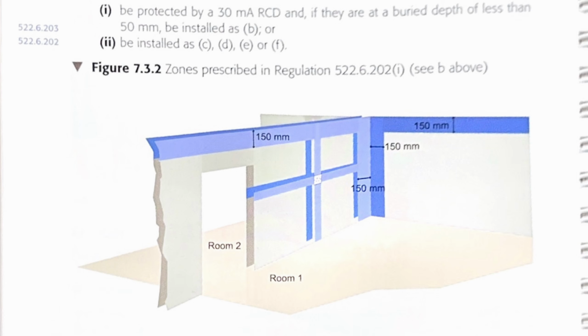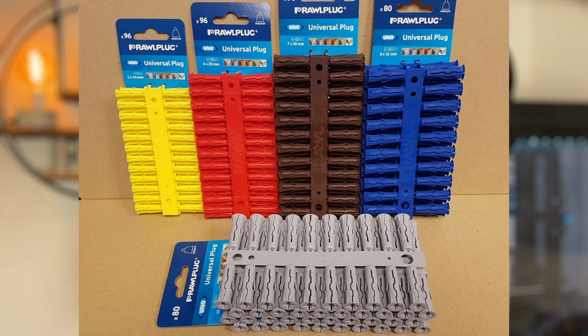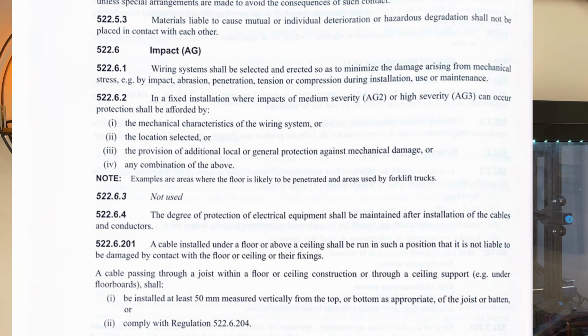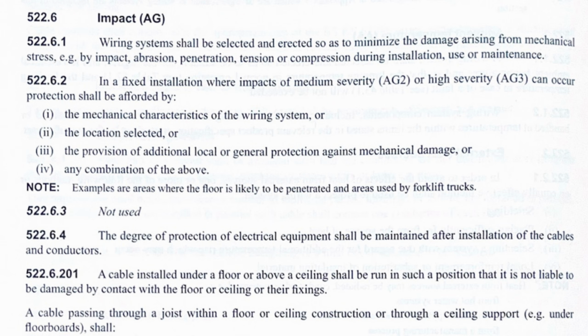Another way to protect cables is to ensure that they're within cable zones. This means that they would be horizontal or vertical from accessories, or to use the corners or edges of walls. This gives us quite a number of areas that we can run cables. Given that most nails or screws for wall fixings are generally going to be under 50mm in length, think of the average rawl plug, there is also requirements to place cables at a depth of more than 50mm, and according to regulation 522.6, if it's below 50mm, then they'd need to be protected to prevent penetration. So that would protect the cable.